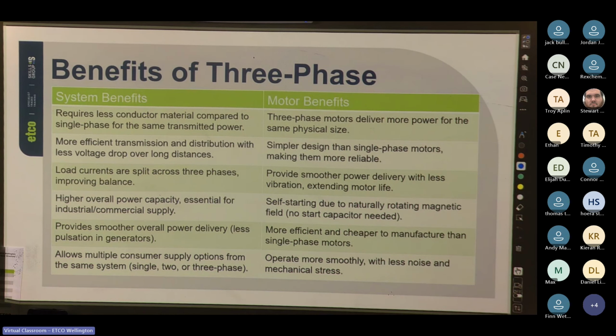Cool. Another advantage, voltage stability. Because the load is shared across two phases instead of just one, there's less chance of the voltage dropping under heavy demand. It also helps the electricity distributor by spreading the load more evenly across the network, and it gives better load balancing. So in a purely single-phase neighborhood, if everyone is drawing from the same phase, it can overload that part of the network. Splitting up consumers across two or three phases balances this out and keeps them more stable.